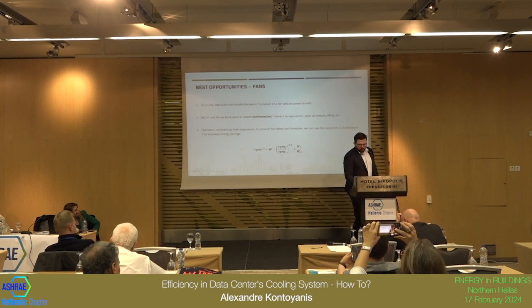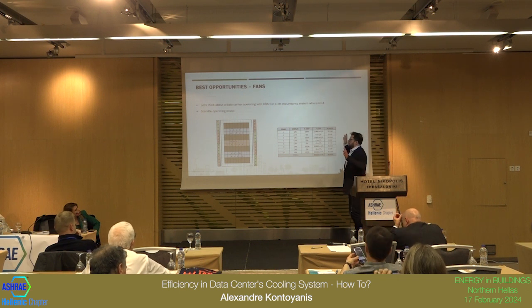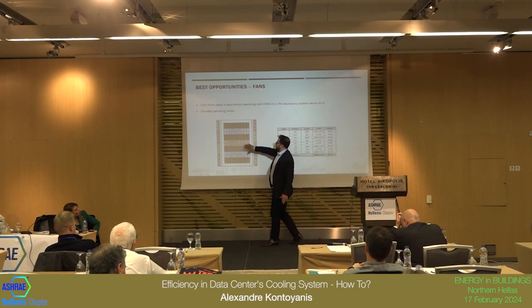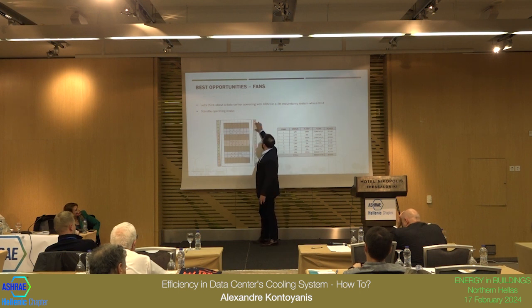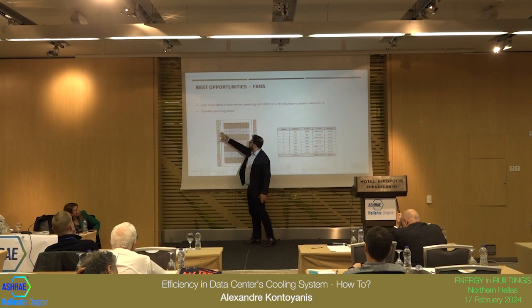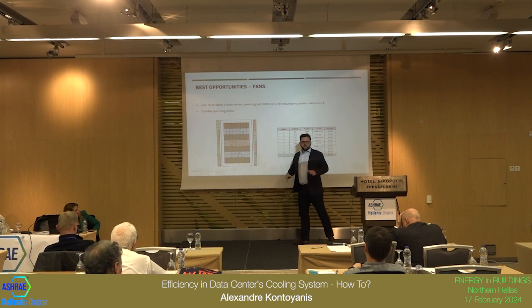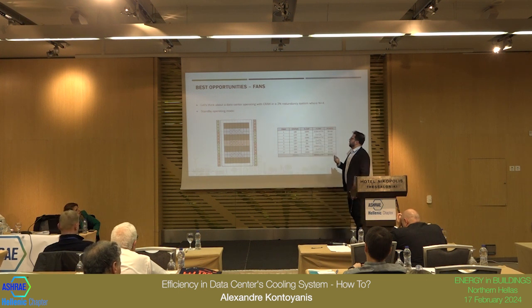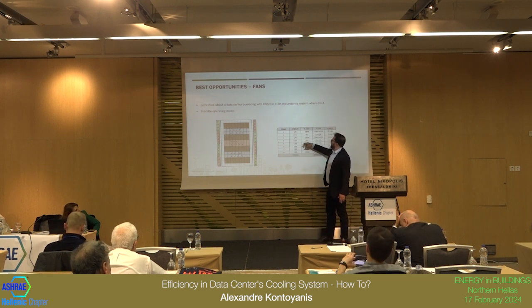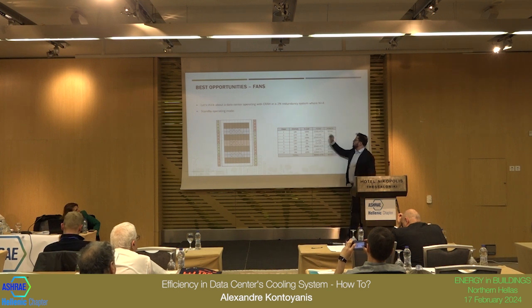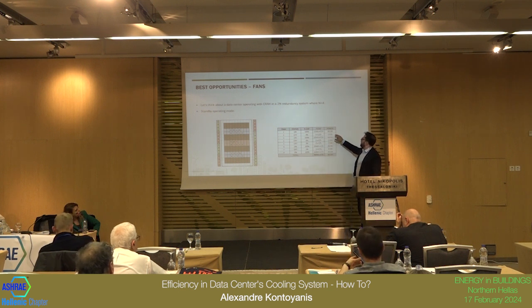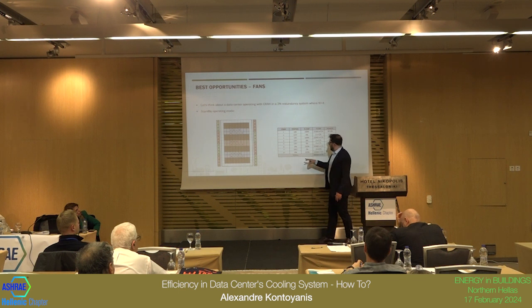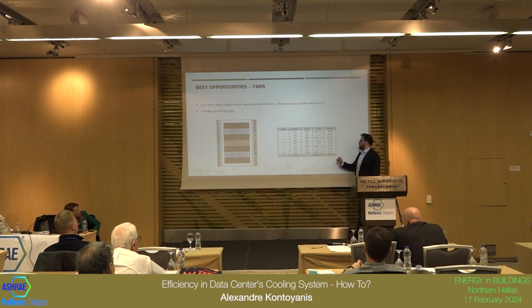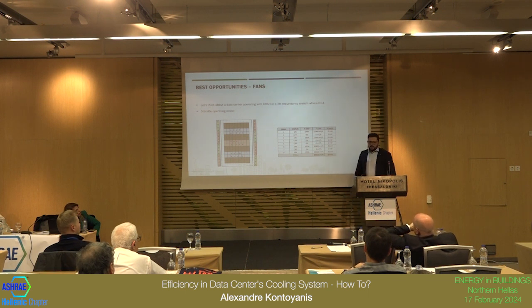Let's see in reality how it would work. This is a fictitious example. We have a data center with racks, cold aisle, hot aisle, and our units on the perimeter. On, off, on, off, on, off, on, off. 2N, so 4 needed on. You can see the table here, from 1, 2, 3, 4 to 8: on, off, 100%, 4%. The flow, 22,000 cubic meters per hour, and the power, 20 kilowatts. So in total, on this data center, we need 88,000 cubic meters per hour of air, and we consume 80 kilowatts.